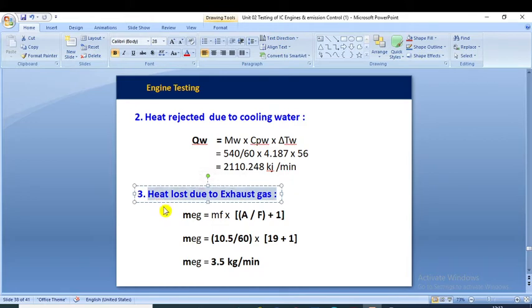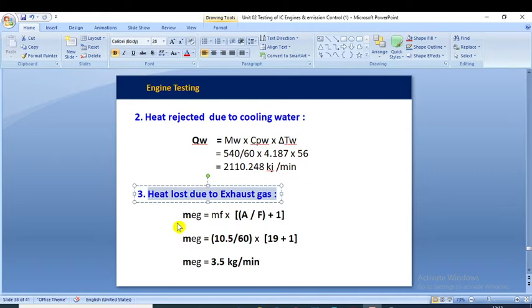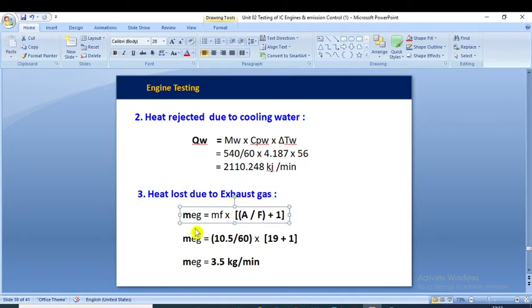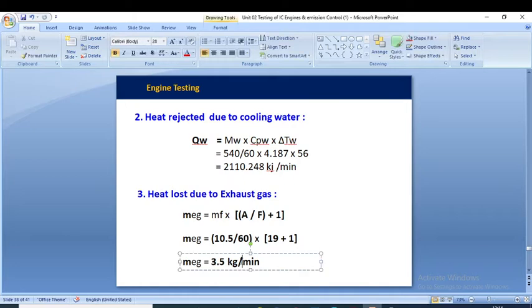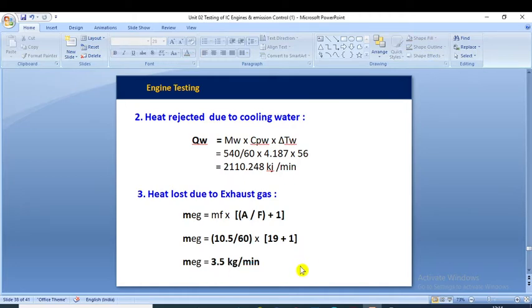Third, we calculate the heat loss to the exhaust gas. To do this we first need the mass of exhaust gas. The formula is: mass of exhaust gas = m_f × (air-to-fuel ratio + 1). So m_g = (10.5/60) × (19 + 1), giving a mass of exhaust gas of 3.5 kg/min.